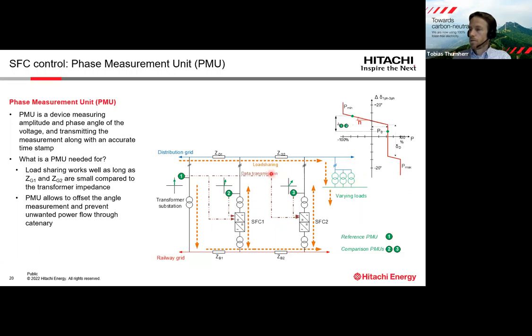So what happens basically if the impedance in the distribution grid is very small compared to the impedance in the catenary: the power towards these varying loads flows through the distribution grid. But if the impedance here is not much smaller anymore than the catenary impedance, then a part of the load will flow through the catenary towards this load, and that's basically not what we want. We want to supply the catenary, we want to supply the trains, but we don't want to offload the distribution grid with the catenary.